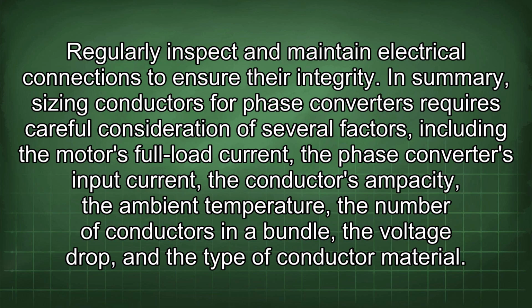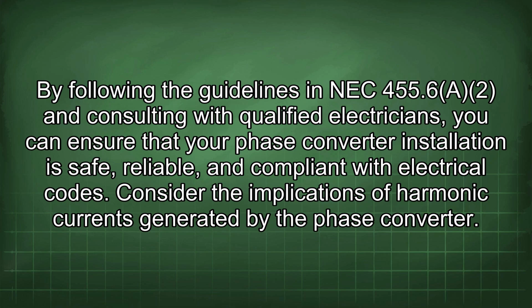In summary, sizing conductors for phase converters requires careful consideration of several factors, including the motor's full load current, the phase converter's input current, the conductor's ampacity, the ambient temperature, the number of conductors in a bundle, the voltage drop, and the type of conductor material. By following the guidelines in NEC 455.6(A)(2) and consulting with qualified electricians, you can ensure that your phase converter installation is safe, reliable, and compliant with electrical codes. Consider the implications of harmonic currents generated by the phase converter.